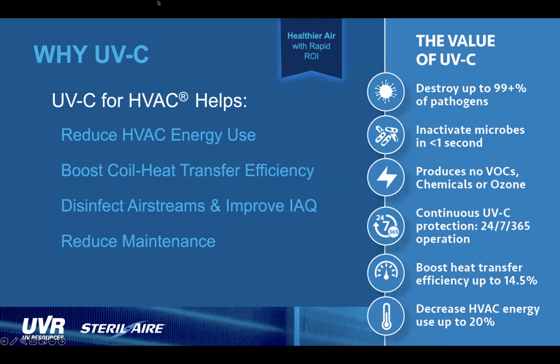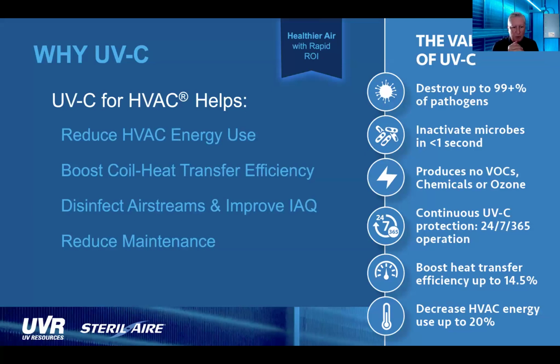Okay, terrific. Thanks, Joe. It looks like we've got a question here about the payback for a UVC system. What is the typical ROI? Good question, Joel. There are a lot of variables. The largest of which is probably what the energy cost is for that particular geography, the air handlers, the age of the system. But typical users pay for their UVC system in less than 12 months. I know in Southern California, where you've got those 24 cents per kilowatt hour rates, we can deliver the payback in 4 months. And extremely fouled coils, older systems, you can get payback in any market in as short as 5 months. So we feel real comfortable with using that 15% savings, and that's going to get you to ROI within a year in almost every case.